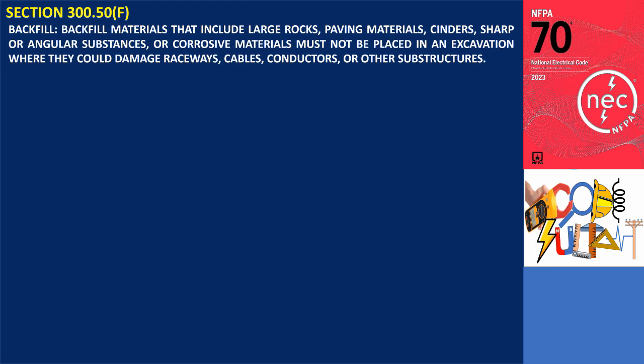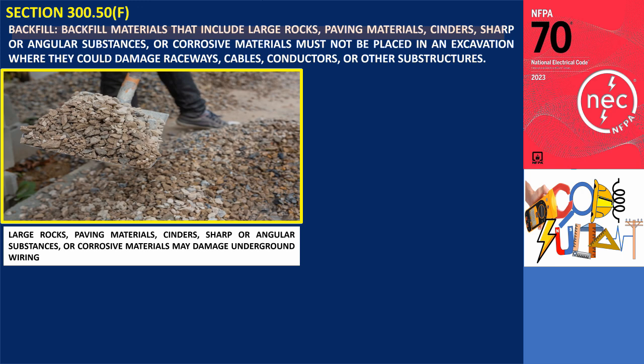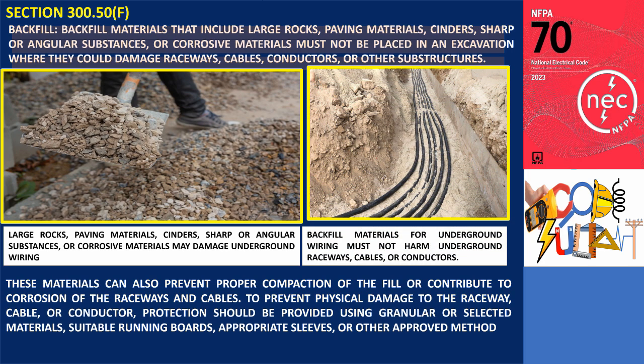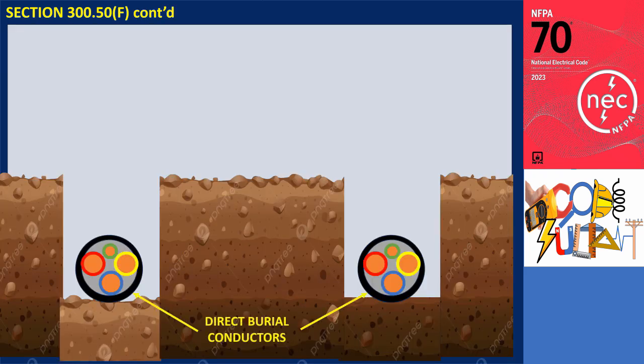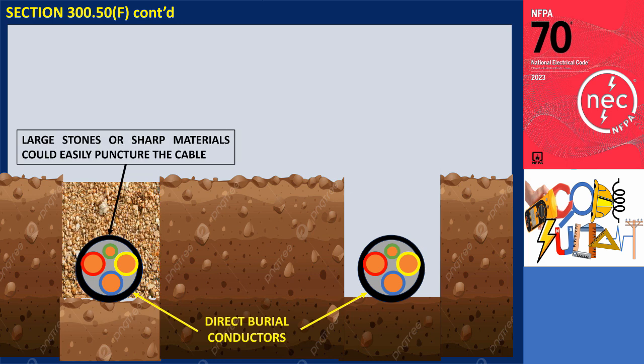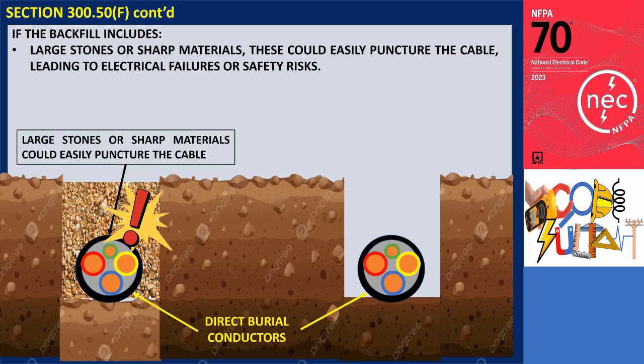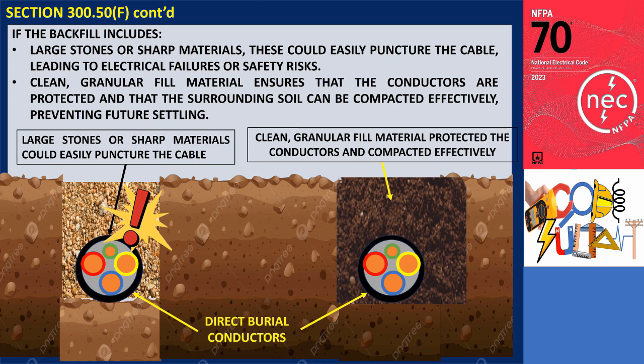Backfill: backfill materials that include large rocks, paving materials, cinders, sharp or angular substances, or corrosive materials must not be placed in an excavation where they could damage raceways, cables, conductors, or other substructures. These materials can also prevent proper compaction of the fill or contribute to corrosion of the raceways and cables. To prevent physical damage, protection should be provided using granular or selected materials, suitable running boards, appropriate sleeves, or other approved methods. For example, if the backfill includes large stones or sharp materials, these could easily puncture the cable, leading to electrical failures or safety risks. Instead, using clean granular fill material ensures that the conductors are protected and that the surrounding soil can be compacted effectively, preventing future settling.